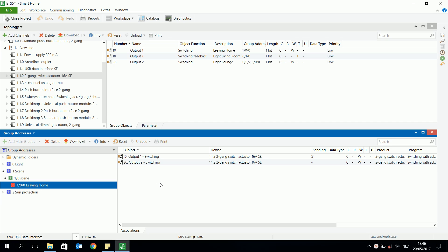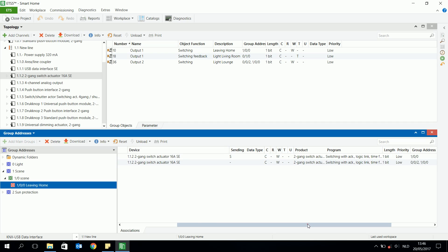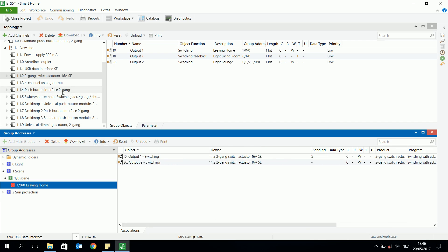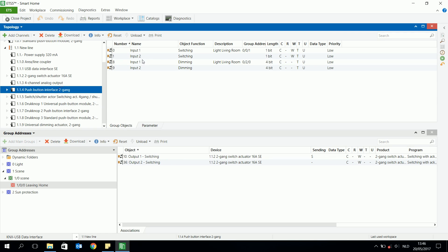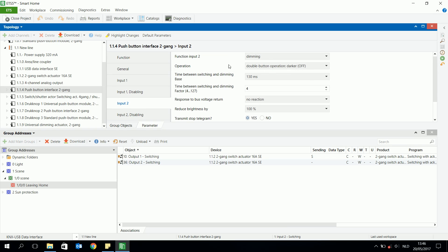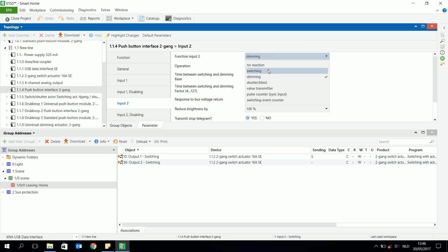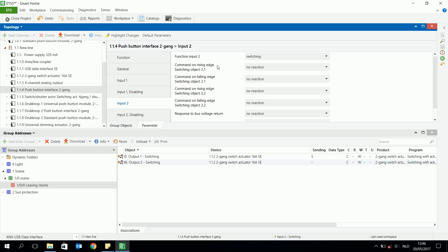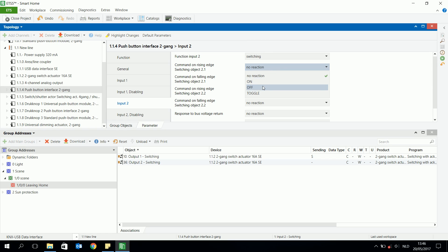I already added two switching objects — object one and object two — and these are two one-bit objects. Then I have to join a push button; I choose input two. I want to make a leaving home scene, so I have to change the parameters into switching, and on the rising edge I will choose an off signal.